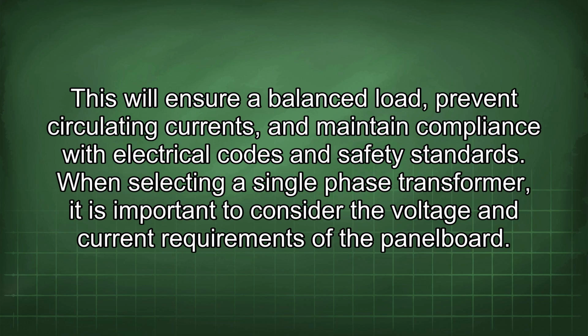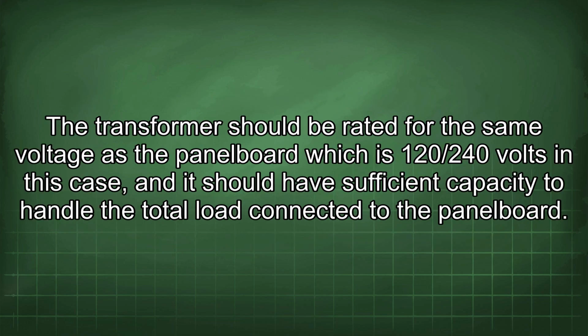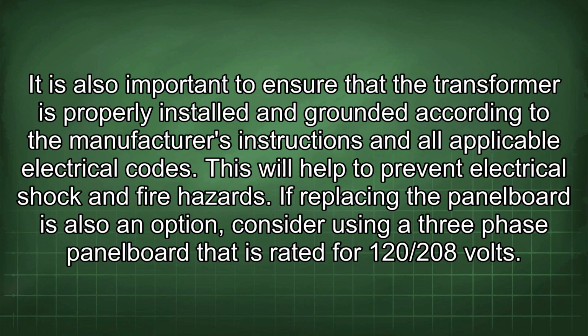When selecting a single-phase transformer, it is important to consider the voltage and current requirements of the panel board. The transformer should be rated for the same voltage as the panel board, which is 120/240 volts in this case, and it should have sufficient capacity to handle the total load connected to the panel board. It is also important to ensure that the transformer is properly installed and grounded according to the manufacturer's instructions and all applicable electrical codes. This will help to prevent electrical shock and fire hazards.